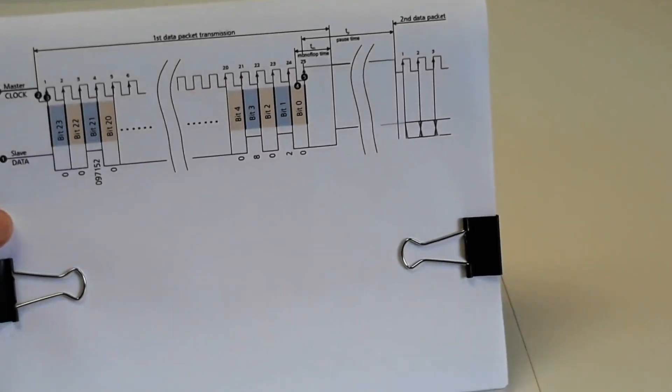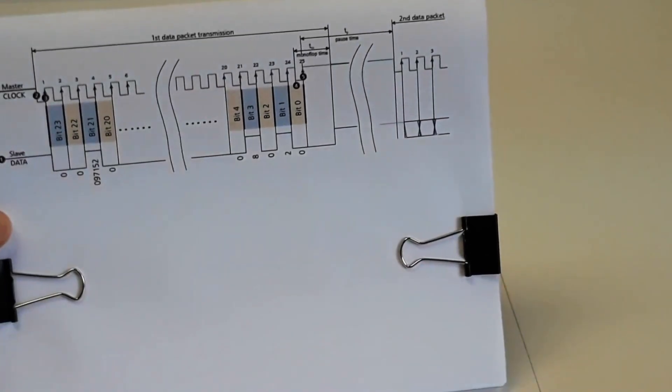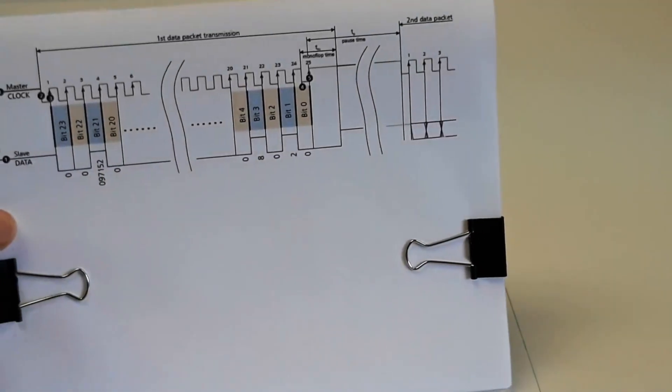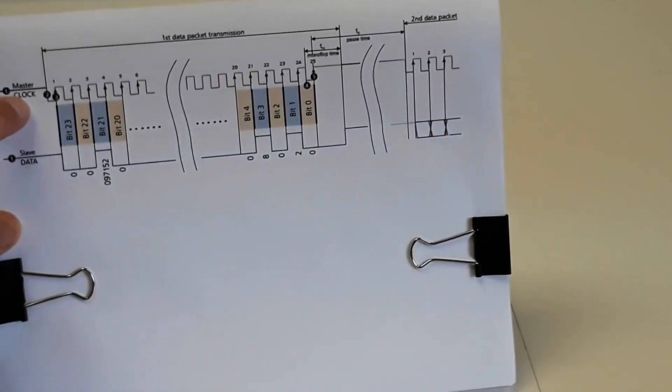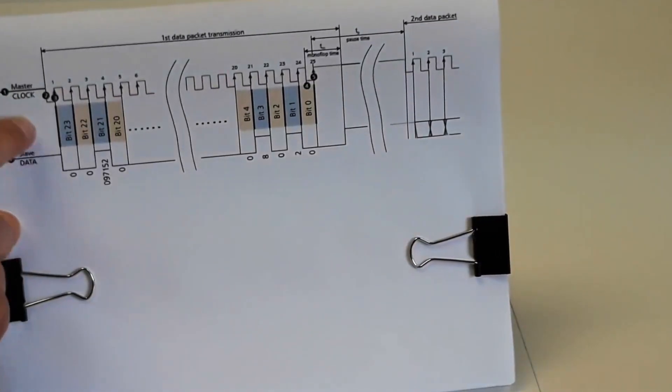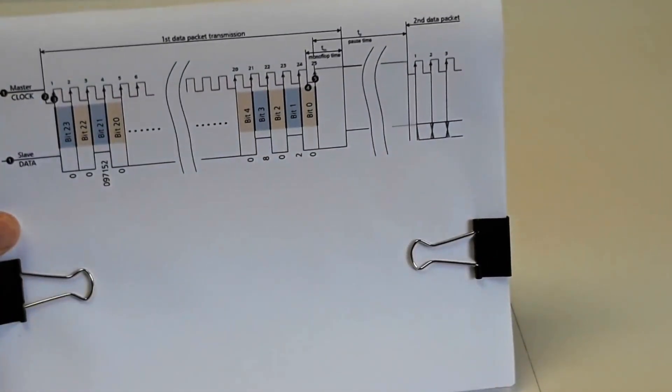SSI encoders act as a master and slave arrangement. The output consists of a pair of square waves for position with a clock input from the master and data output from the slave. The master is typically like a PLC or motor drive.